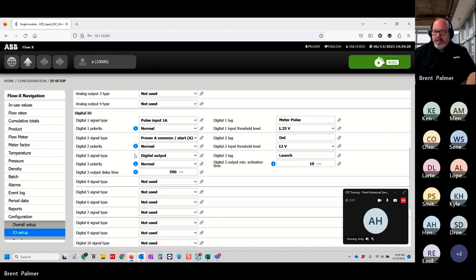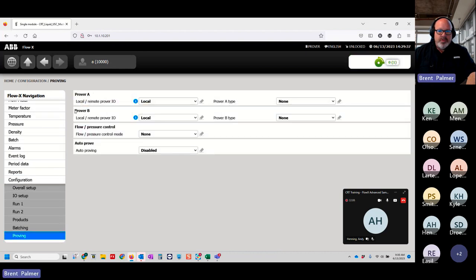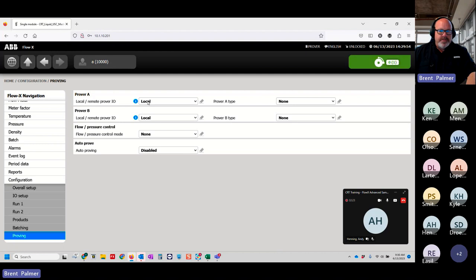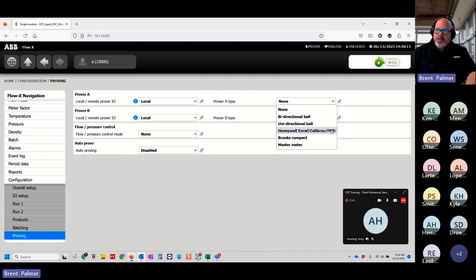Now I'll set up the prover. Going into the Prover menu, I can have both Prover A and Prover B, and I can also set up flow and pressure control and auto proving. For now I'll stay with the basics. I'll tell it whether the prover is local or remote — it's local — and then specify the prover type: is it a ball prover unidirectional, or is it Honeywell Enraf, Calibron, FMD, Meter Engineers new prover, or Magnet Prove? These are all piston provers. The only anomaly is the Brooks Compact Prover, which requires a certain pressure held on the plenum and has additional settings. I'll treat this as a normal piston prover and hit OK.